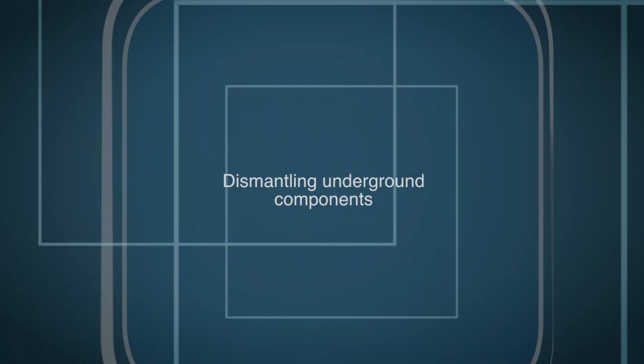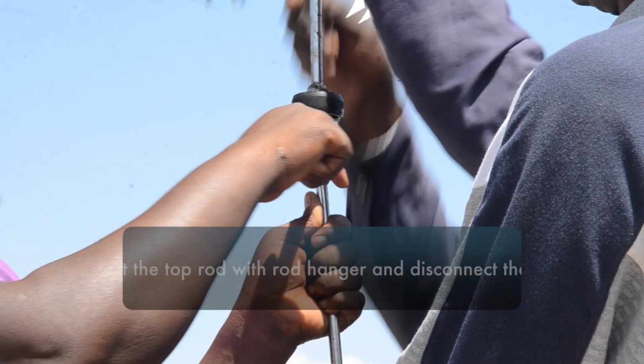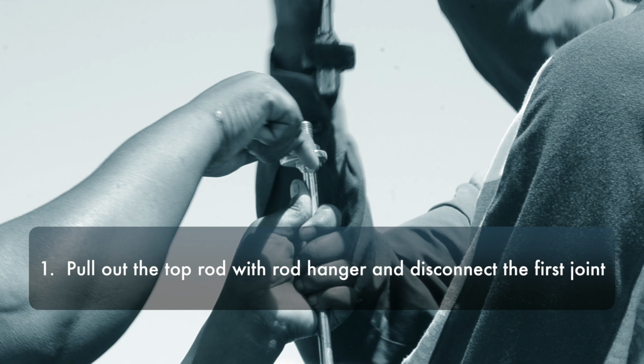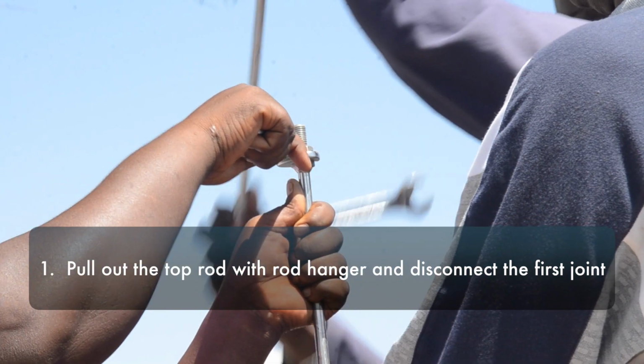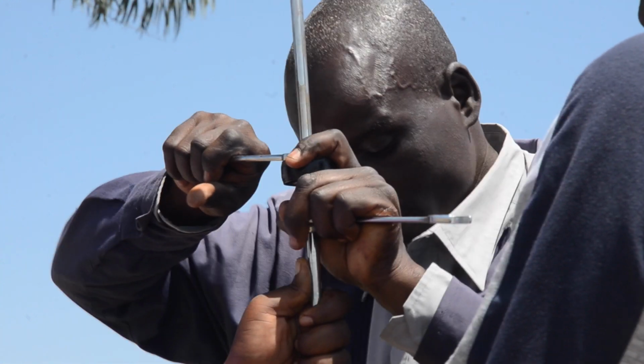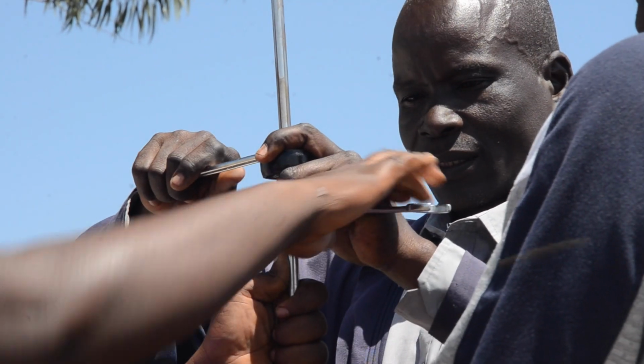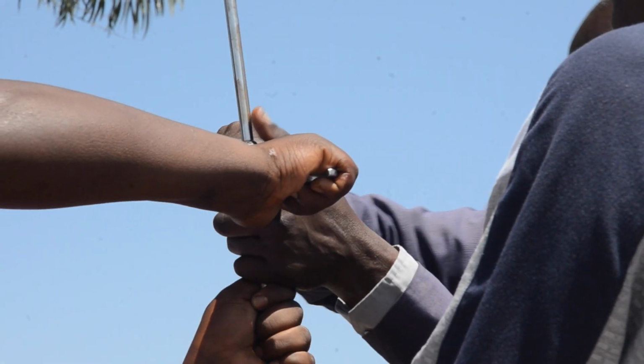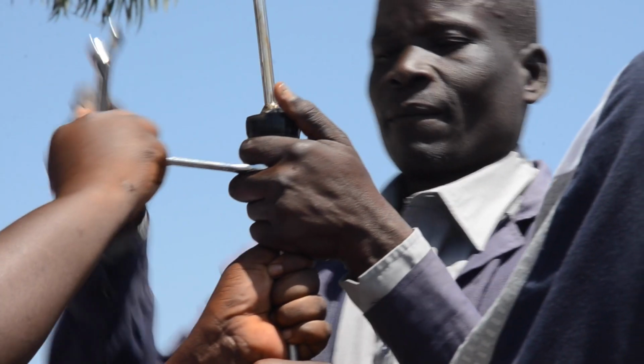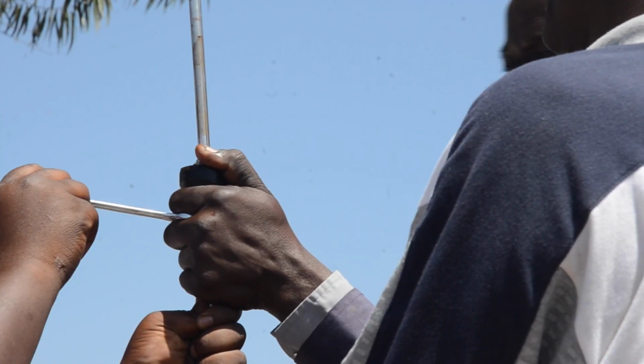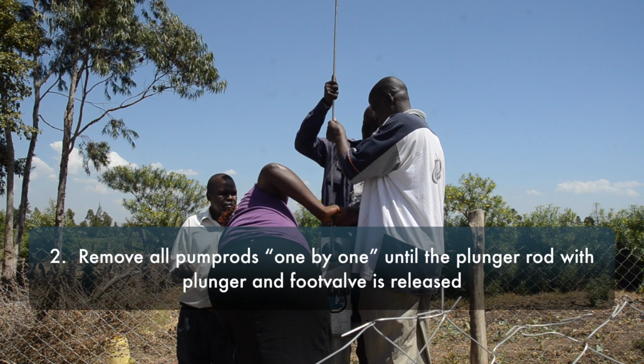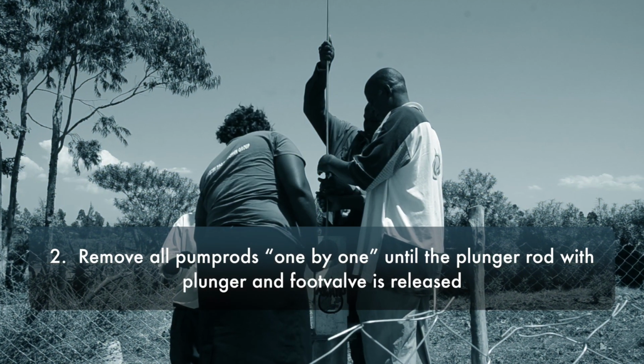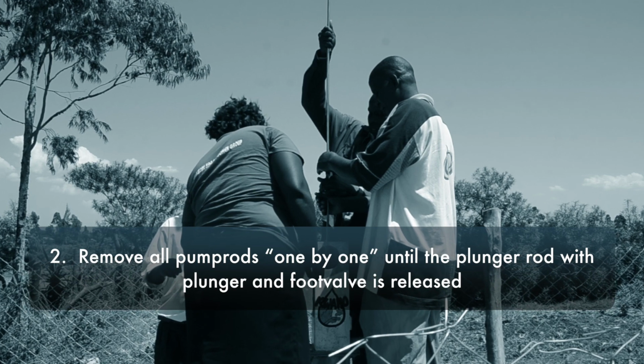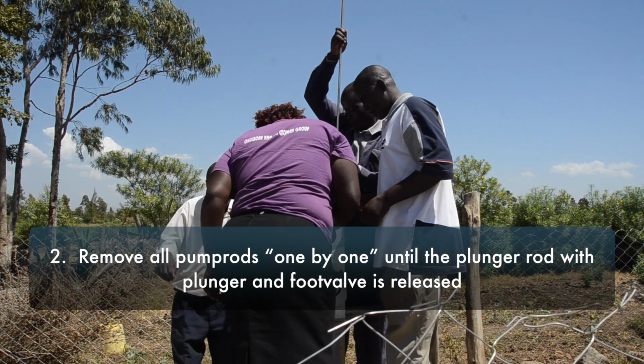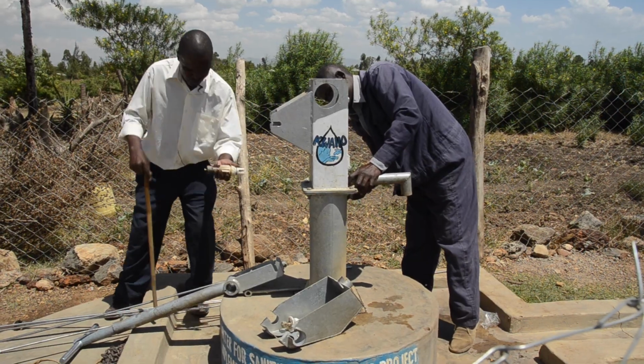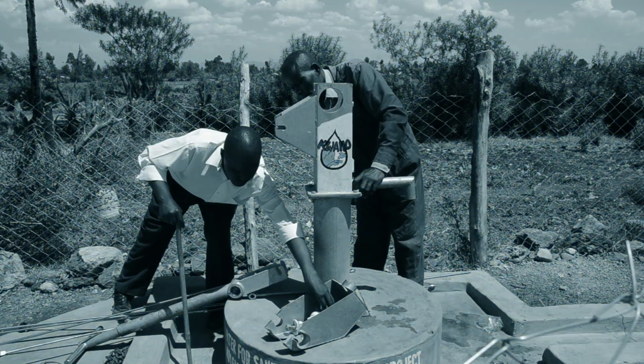To do that, you must take the following steps. 1. Pull out the top rod with the rod hanger and disconnect the first joint. It is important that the two helpers ensure that they don't let loose the hanger. Remove all pump rods one by one until the plunger rod with the plunger and foot valve is released. Make sure that all rods are neatly placed near the pump and are in a clean place.